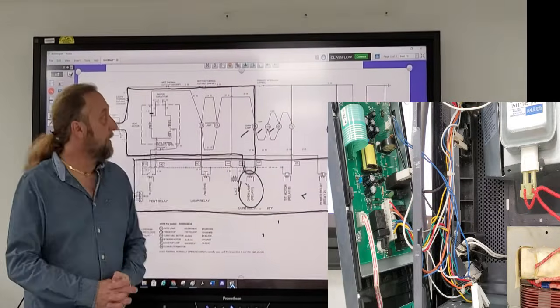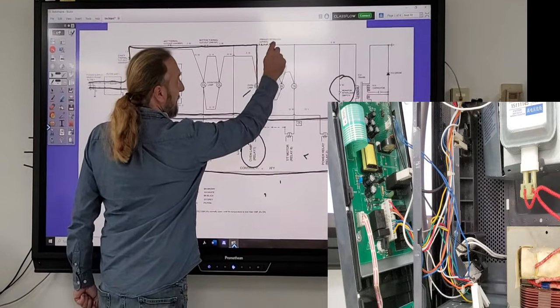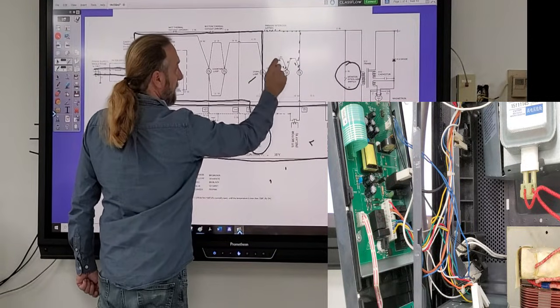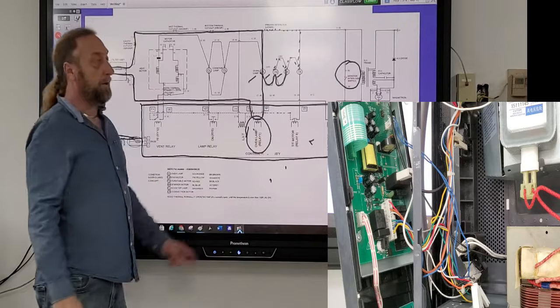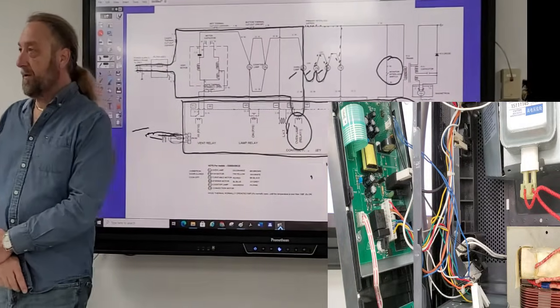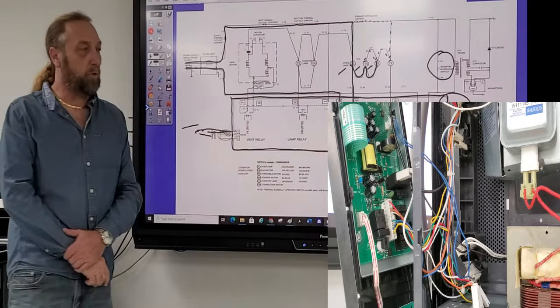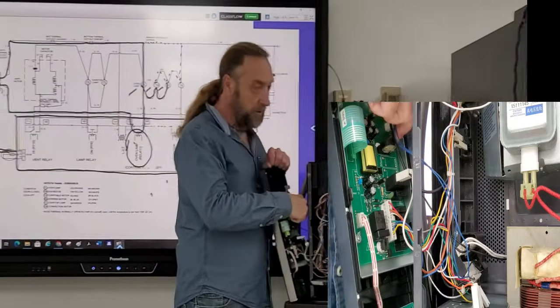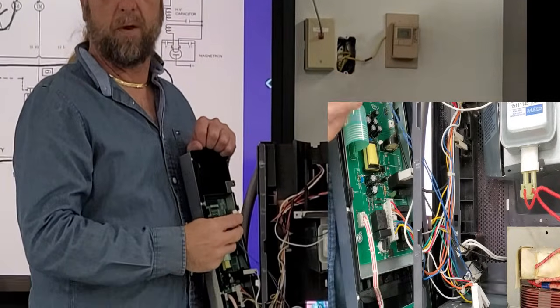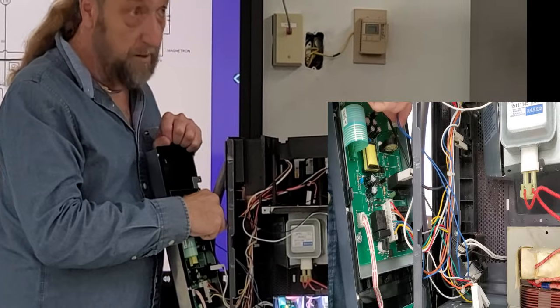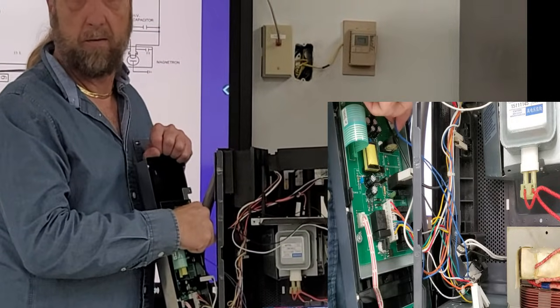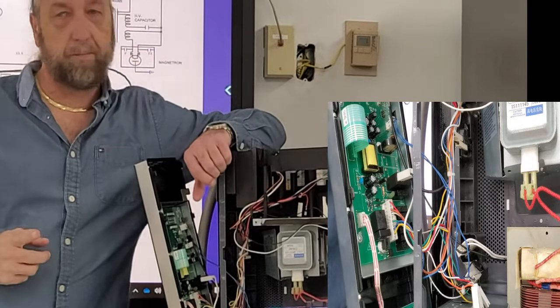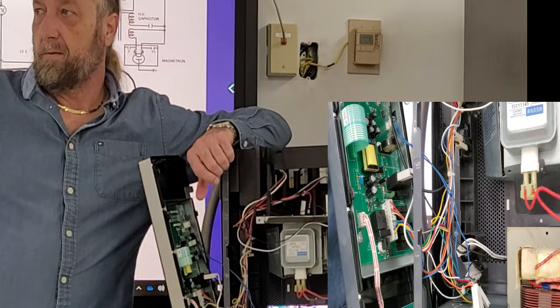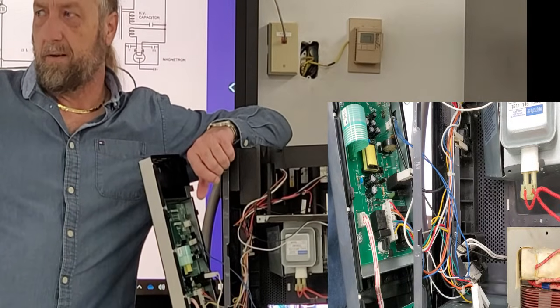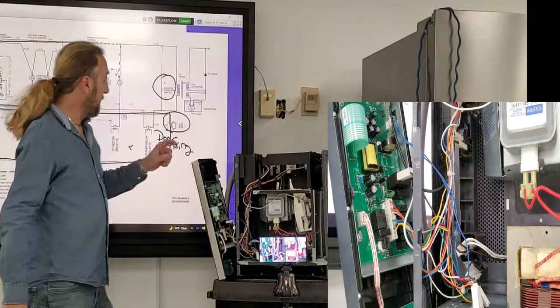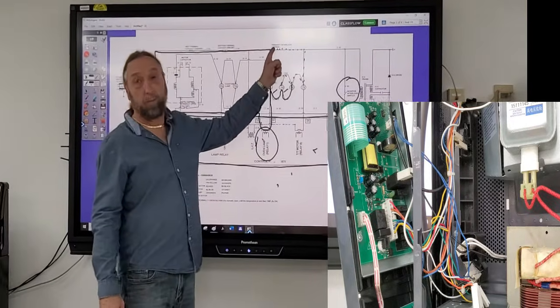Anybody know? Because they have to go through the other door switch in order to work. If that door switch is not closed, the fan doesn't come on. So watch this. I disconnected the door switch while it's open. I opened the door. The light came on. We hear the relay, right? We're hearing that relay number 1 click. But the fan didn't come on. But wait, when I open the door, the fan's not supposed to come on, right? Yeah, but when I open up the door, I opened this one and I opened that one.